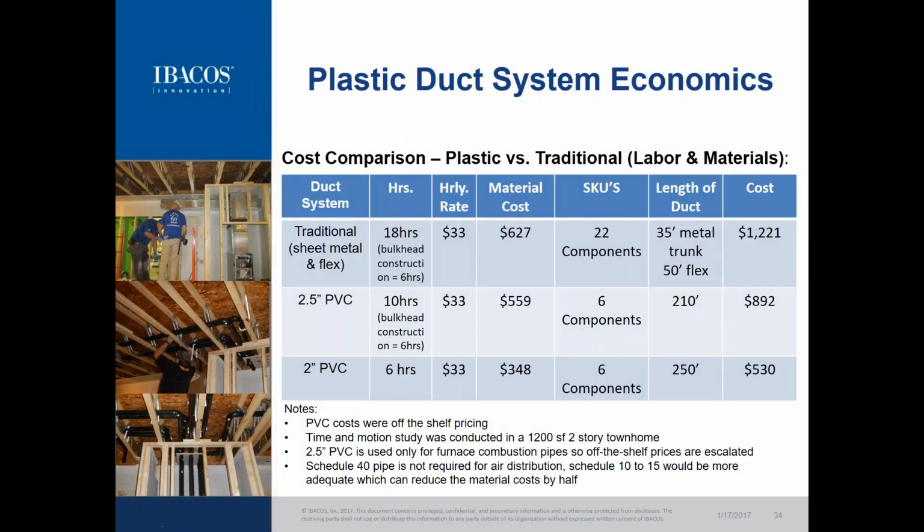And then lastly, from an economic standpoint, and this is probably one of the most important pieces from a builder and market penetration standpoint, we built a framed townhome in our warehouse to mock up and understand the time and motion of this system. So we mocked up a traditional sheet metal with flex duct branches, and then we also mocked up a 2.5-inch PVC scenario, and then a third one being a 2-inch PVC.